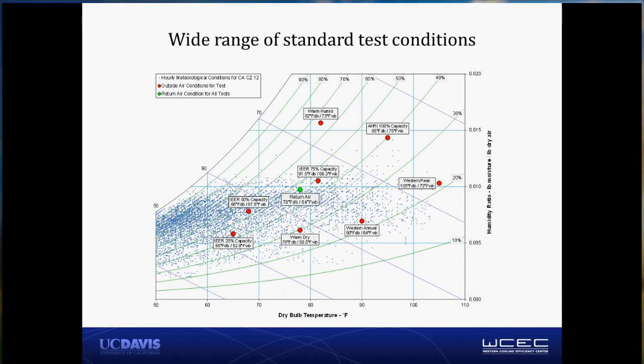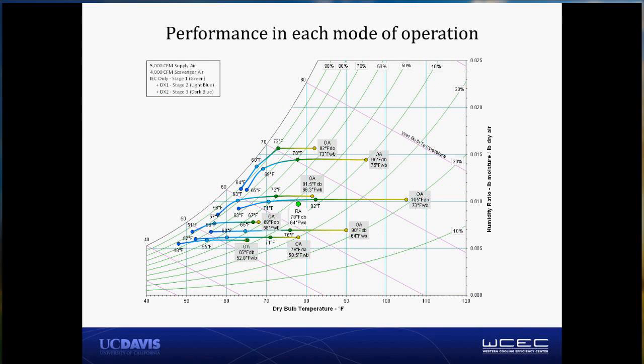We're using the two Western Cooling Challenge performance conditions, the peak condition and the quote annual condition, which represents like a warm, dry day in California climates. And then we're also trying to replicate AHRI's 100% capacity condition used for EER and the IER metrics, as well as the part load conditions used by AHRI to capture their IEER, the Integrated Energy Efficiency Ratio performance for commercial equipment. A couple other points that also map from other ASHRAE methods of test. We've got a pretty standard map we're using to evaluate the equipment, and we've marked out performance for the system in all modes of operation.